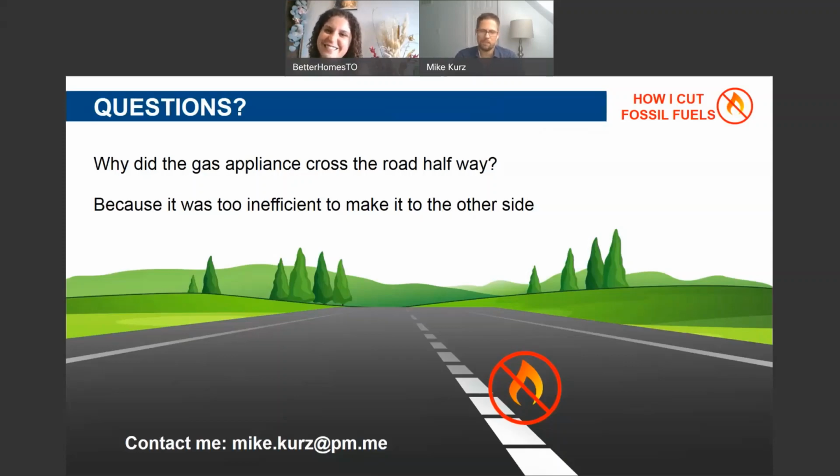That's fantastic. Yeah, that's exactly what I was talking about. This one that I installed is a cold weather heat pump. It supposedly works down to -30 Celsius. And my data suggested that I won't even need a supplemental resistance heat until it gets down to -25 out. So I think that is, in our climate, definitely something you can push back on with your contractors.